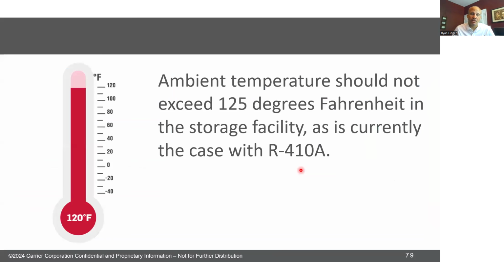You're not supposed to store the refrigerant above 125 degrees for R-32 and R-454B. That is the same exact temperature limit as 410A. And the reason it is the same is you saw the PT chart earlier. The temperature and pressure relationship of these refrigerants is all similar. So if we get to 125 degrees, that means I'm at approximately a certain pressure, right? 400 and some psi, and I'm trying to keep it under that so I don't bust this thing.